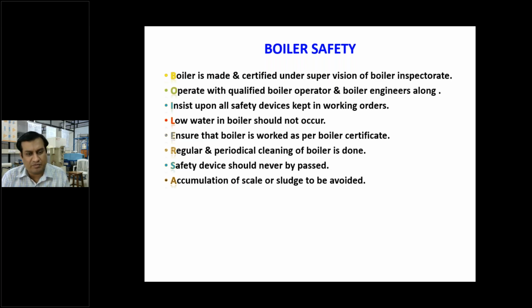So you have to check all the parameters, and that is why before feeding the water, all the parameters should be checked, like pH of the water, BOD, COD, DO, alkalinity, acidity, some foreign materials, especially the salts, the TDS, TSS, that is total dissolved solids or total suspended solids, total solids, etc. All the parameters should be checked before feeding that water, to avoid scale and sludge formation.